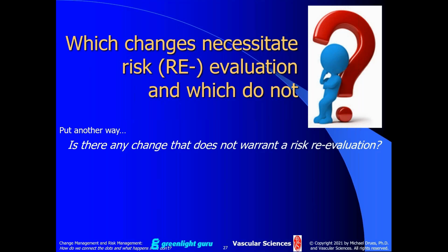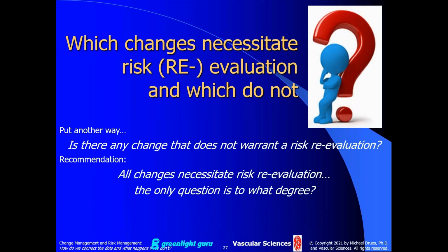But I, as a biomedical engineer and as a regulatory consultant, somebody who's been playing this game for about 30 years, can't think of any change that would not warrant some form of risk reevaluation. Again, as I said earlier, it doesn't make sense to treat all of these reevaluations the same. We have to triage them. But every change that we make, and I'm going to share some examples in a moment, should trigger some level of risk reevaluation.